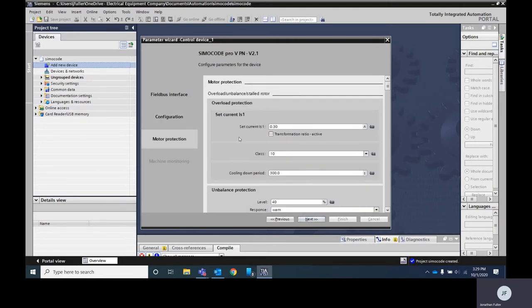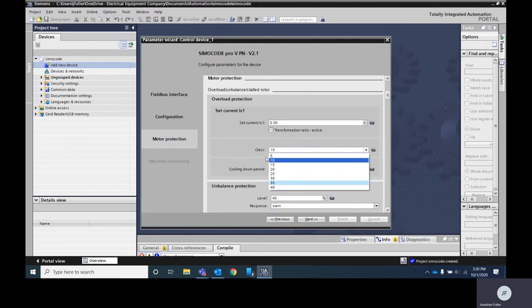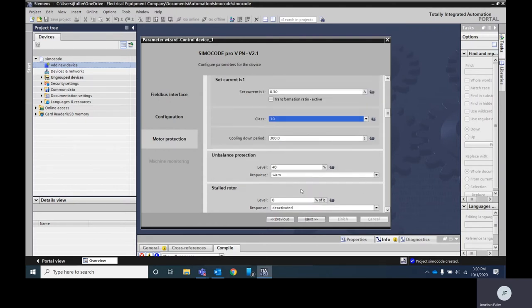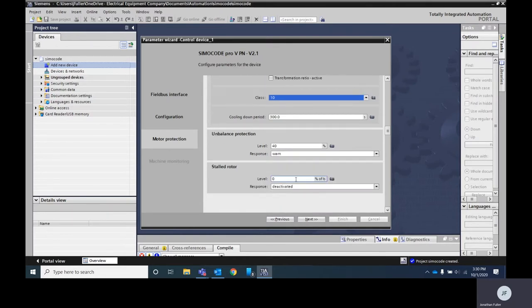Here this is where you're going to need to enter some of your overload protection information off of your motor. You'll want to know your set current. You can set the overload setting for your class and you see you have here all the way from five to 40. You can go in and put in your level of your stalled rotor unbalanced protection. Once you've entered those values go ahead and hit next.